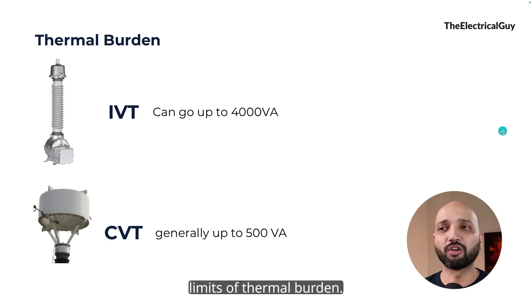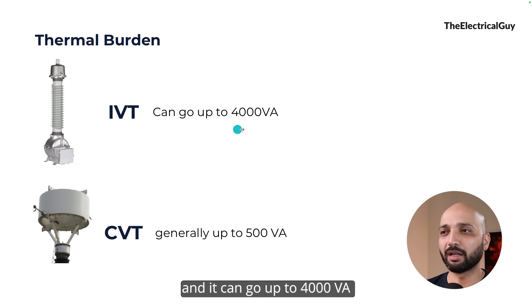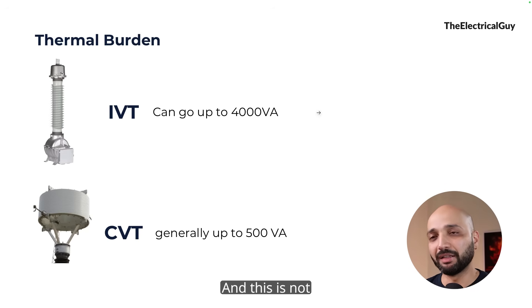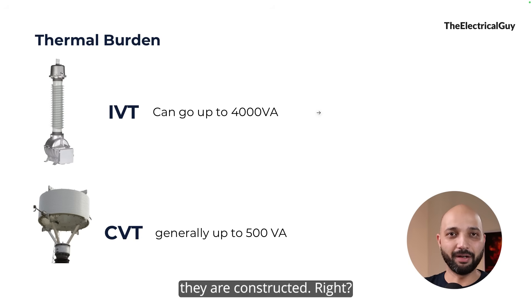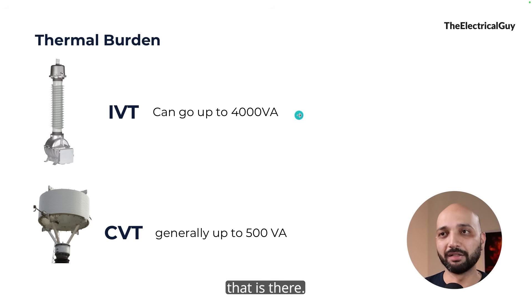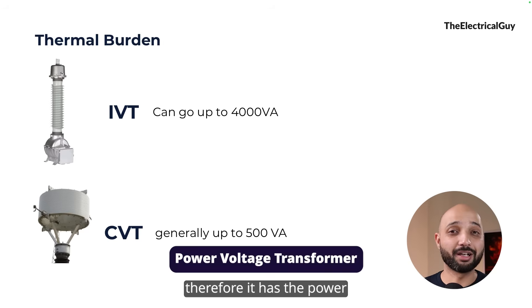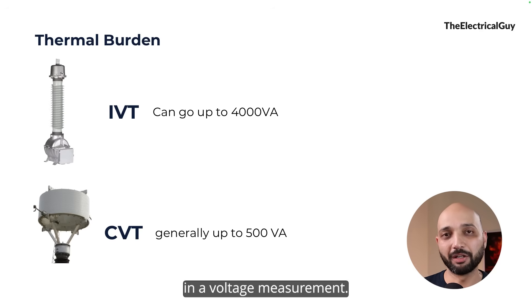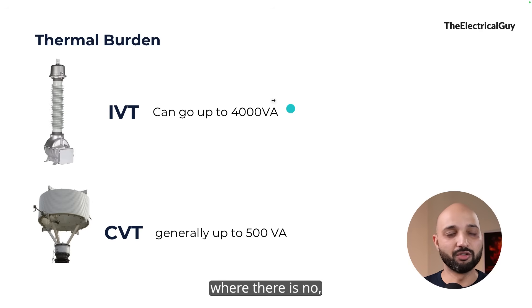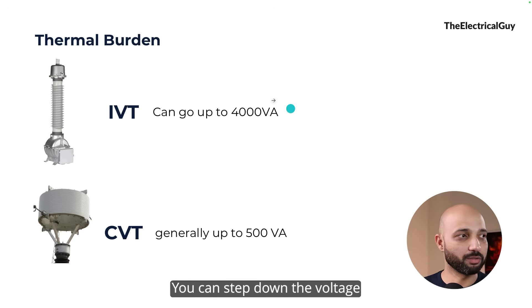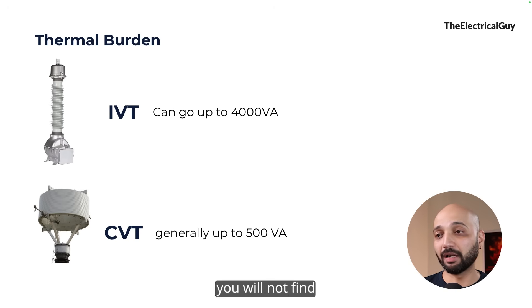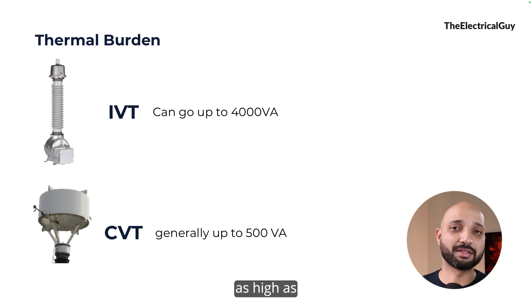IVTs have very high thermal burden limits — they can supply up to 4,000 VA depending on the configuration. This is not because they are inherently superior, but because of how they are constructed. There are even special types called power voltage transformers, which can supply significant amounts of power while also performing voltage measurement — useful in remote areas where no active grid is available. CVTs, on the other hand, do not have thermal burden as high as IVTs; they are limited to a few hundred volt-amperes.